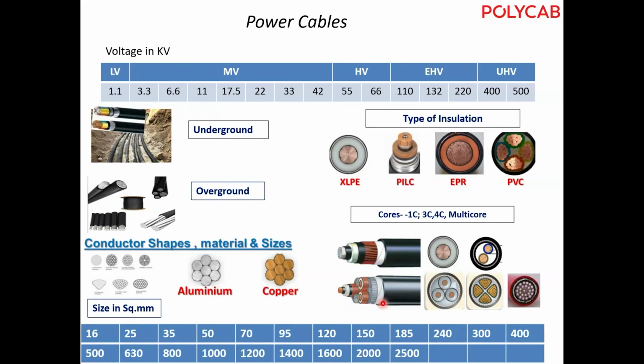So cable accessories come for 1.1 kV to EHV cables. LV is 1.1 kV. Medium voltage, MV, is 3.3, 6.6, 11 kV. So 3.3 to 42 kV is medium voltage. High voltage is 55 kV and 66 kV. Then EHV is 110 kV to 220 kV and UHV is 400 and 500.